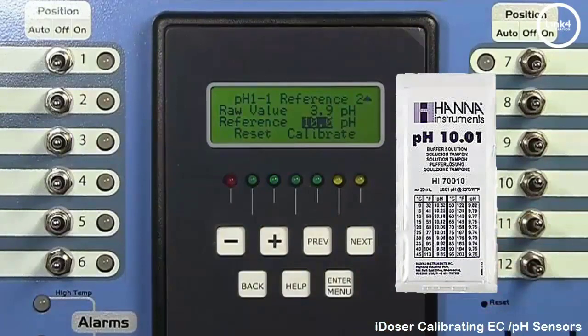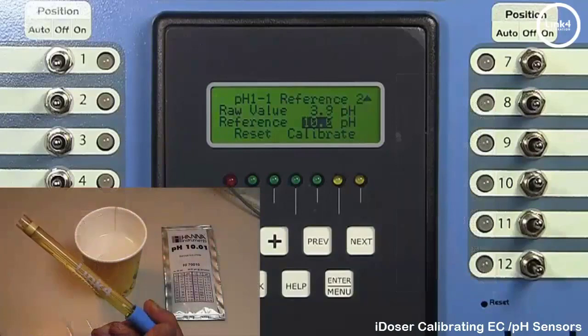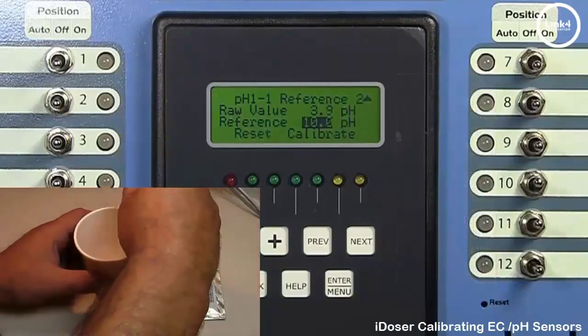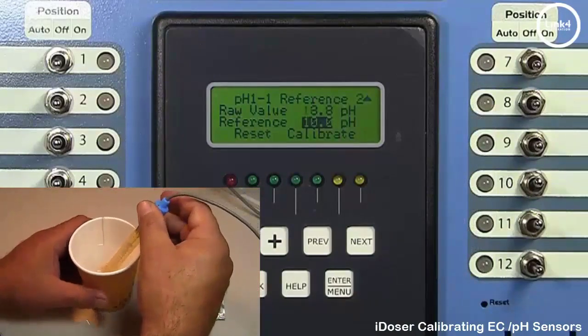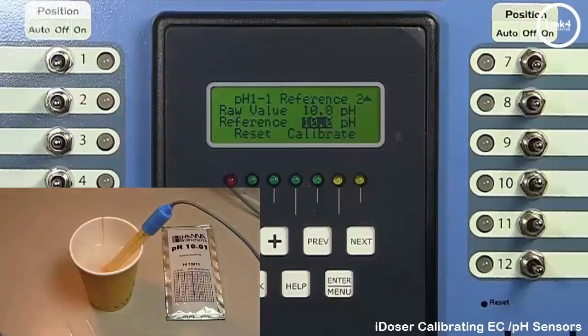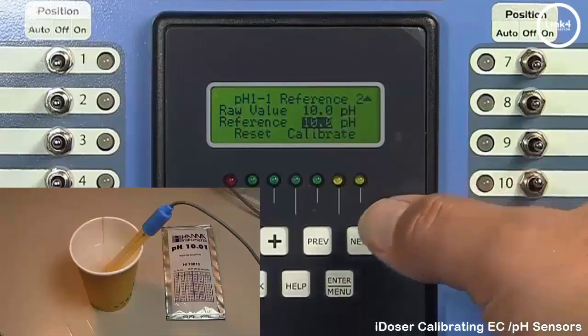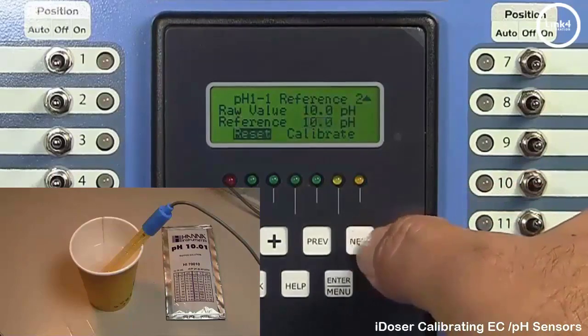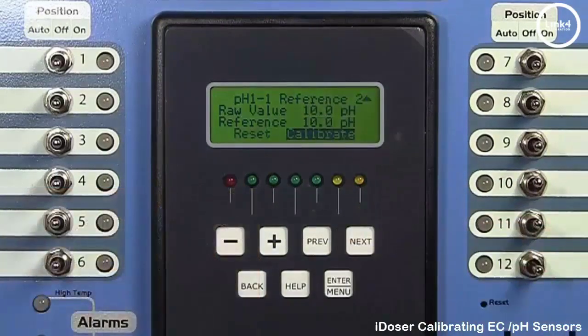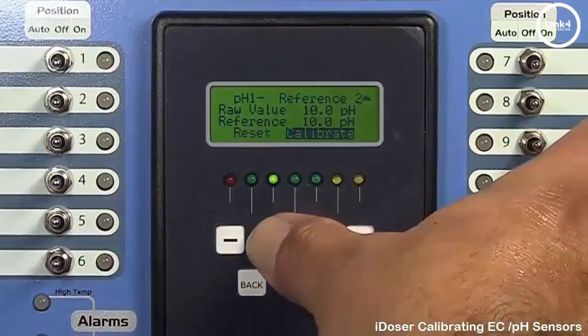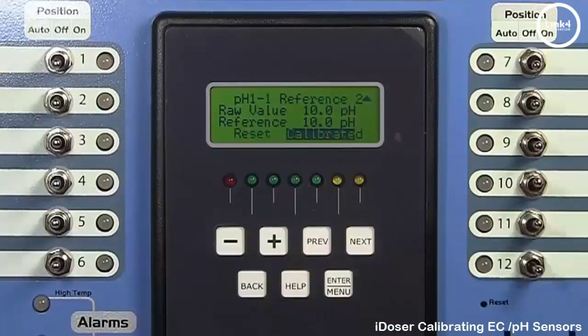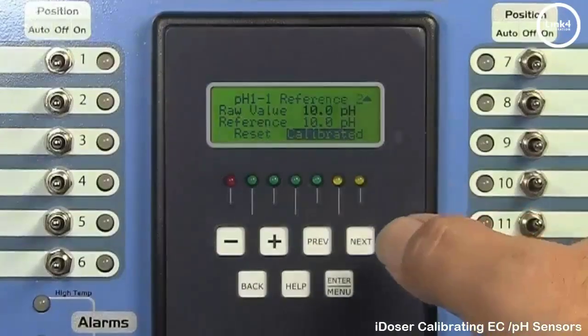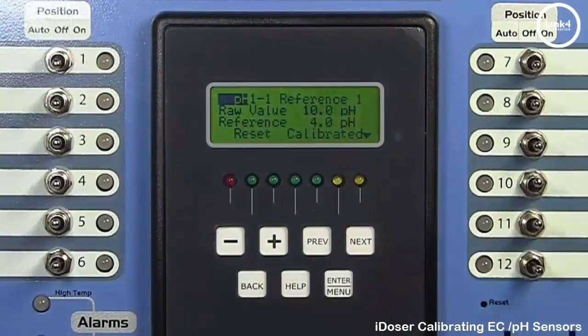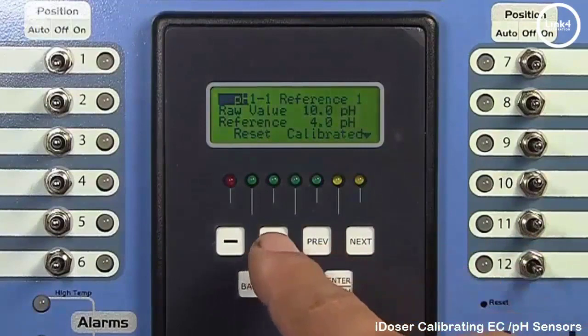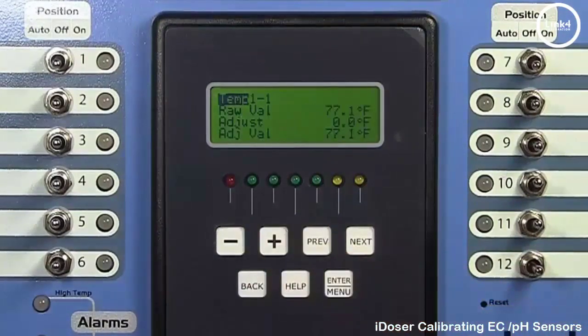Next, we will open the pouch of our 10 pH solution. We will insert our pH sensor into the solution, stir, and wait for a raw value to settle. Once this value has settled, we want to go back to the controller and simply hit Next to highlight Calibrate, and then hit plus till the controller displays calibrated. And hit Next till you get to the Reference 1 screen. And then hit plus. And finally we have temp.